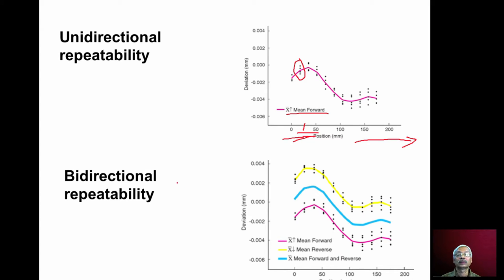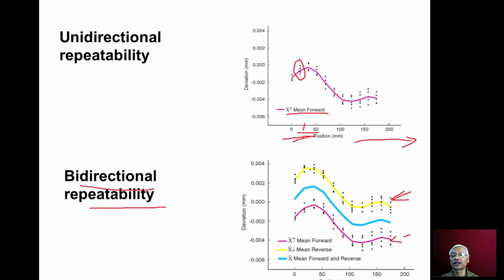Similarly, in the reverse direction also we should conduct the experiment to get the bidirectional repeatability performance. This curve shows the error in the forward direction, the yellow line indicates the error in the reverse direction, and the blue curve indicates the average of both. These experiments should be conducted for all three axes — x-axis, y-axis and z-axis — and then we will know what is the repeatability of the stage.